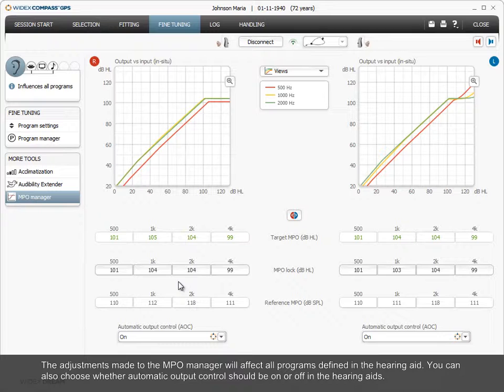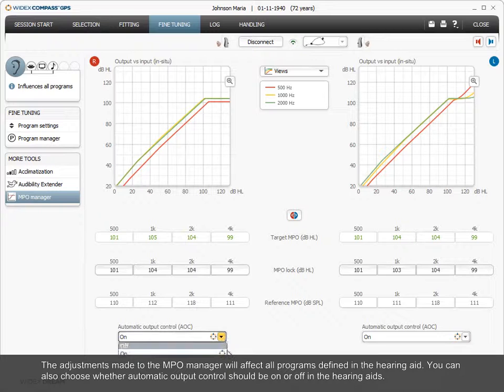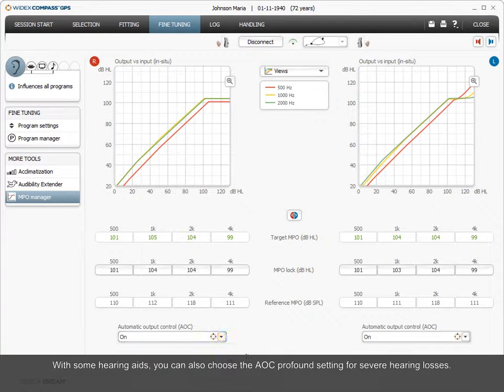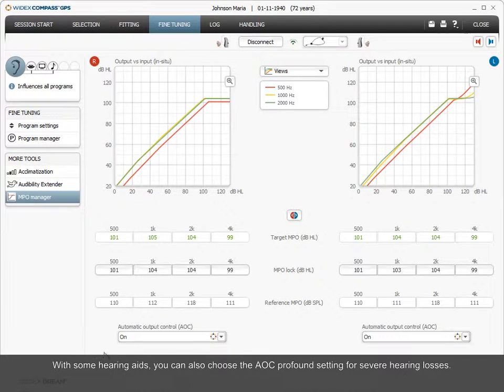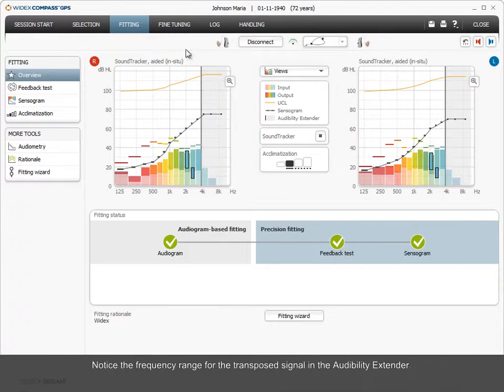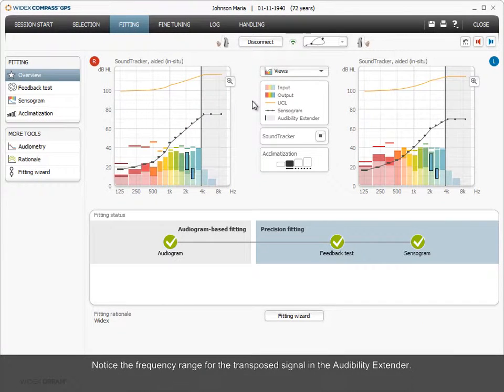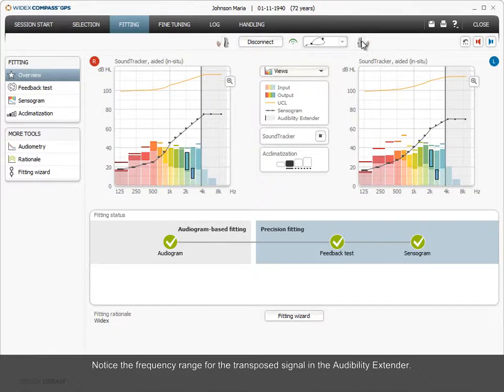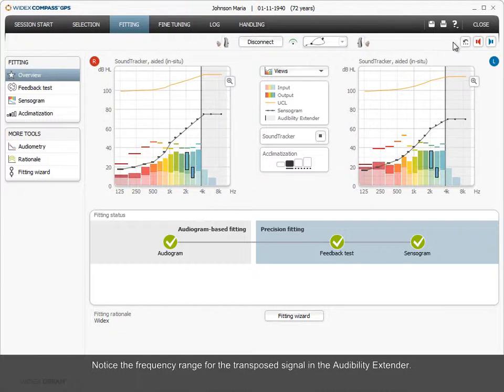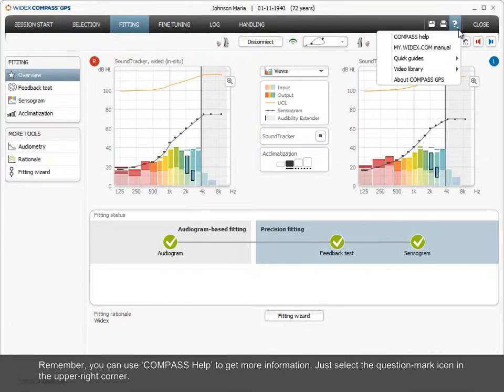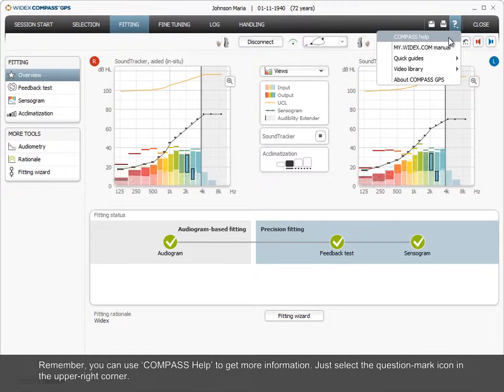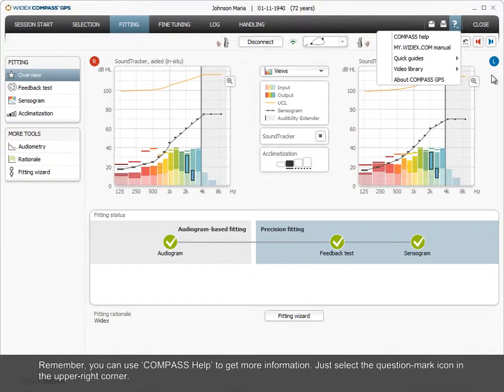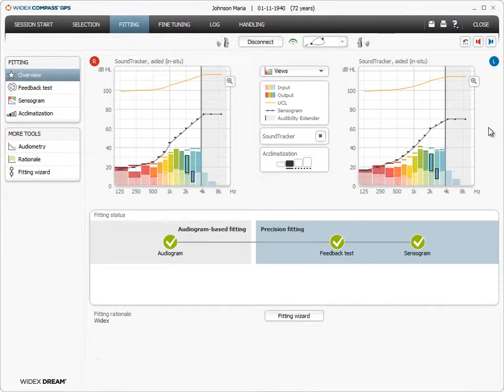You can also choose whether automatic output control should be on or off in the hearing aids. With some hearing aids, you can also choose the AOC profound setting for severe hearing losses. Notice the frequency range for the transposed signal in the audibility extender. Remember, you can use COMPASS help to get more information. Just select the question mark icon in the upper right corner.